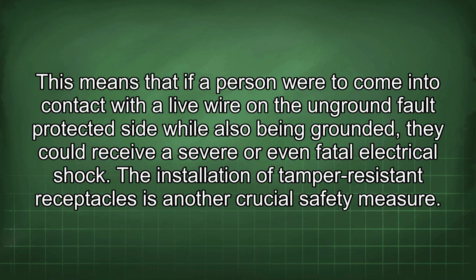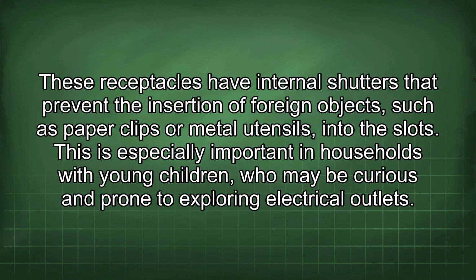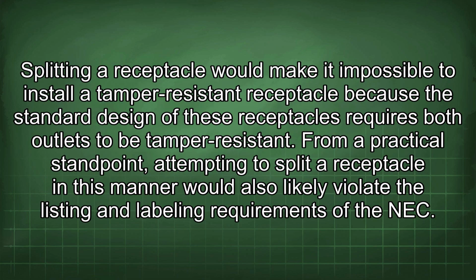The installation of tamper-resistant receptacles is another crucial safety measure. These receptacles have internal shutters that prevent the insertion of foreign objects, such as paper clips or metal utensils, into the slots. This is especially important in households with young children who may be curious and prone to exploring electrical outlets. Splitting a receptacle would make it impossible to install a tamper-resistant receptacle because the standard design of these receptacles requires both outlets to be tamper-resistant.